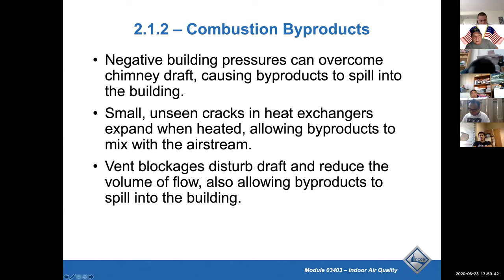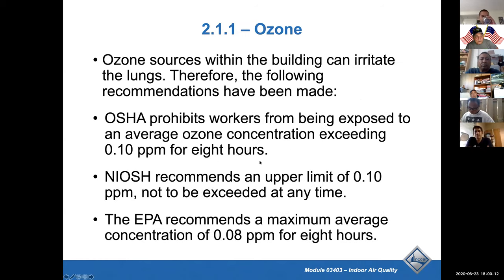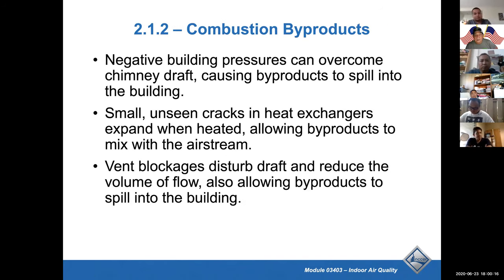Negative building pressure. I think my building's positive pressure, and that keeps things from seeping in from the outside. And then we have an exhaust vent that exhausts from the restrooms and stuff. It's talking about heat exchangers, where small cracks in heat exchangers expand when heated, allowing byproducts to mix with the airstream, and vent blockages. This is talking about a boiler vent or a chimney vent. If somebody blocks the vent off, then whatever's burning gets into the building. Okay.